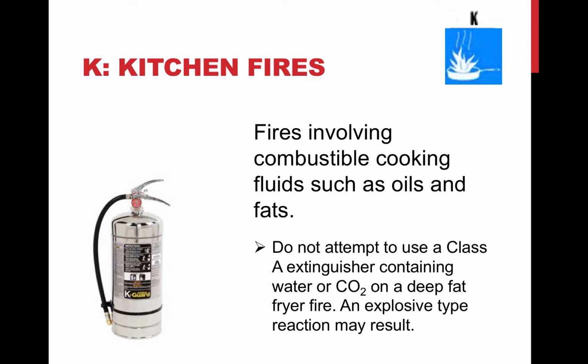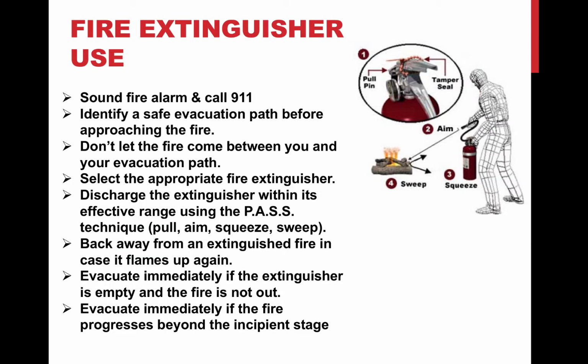Don't use a Class A extinguisher, which is water or CO2, on a deep fat fryer. An explosion can result. Water and oil do not mix. Don't do it. Okay, so to use a fire extinguisher properly, first of all, sound a fire alarm and call 911. Identify a safe evacuation path for yourself before approaching the fire. Do not ever let a fire come between you and your evacuation path.